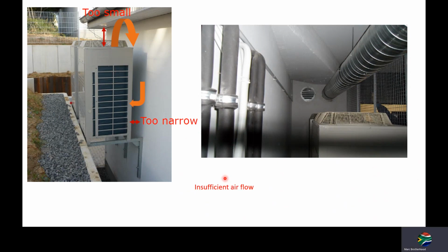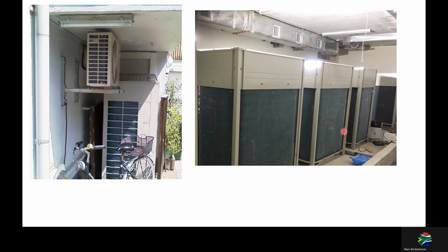Here too, we can see insufficient airflow. It's too narrow. Top discharge, you're just going to short cycle hot air. So this is poor installation practice. Here as well, you can see there's going to be a recirculation of hot air, which wasn't taken into account, and either a supply or return duct running right over this. So this unit system is going to run with very high head pressures. More photos of bad installation practice. Further going to result in high head pressures, a lot of high head and recirculating temperatures. Very poor installation practice.